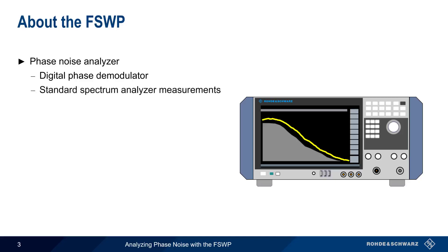Let's start with a brief overview of the FSWP. The Rohde & Schwarz FSWP is a phase noise analyzer that measures phase noise directly using a digital phase demodulator. The FSWP can also make many spectrum analyzer measurements, such as transient analysis, spur search, etc. It can also be configured with a second measurement path that allows phase noise measurements using the cross-correlation method, improving both speed and sensitivity.